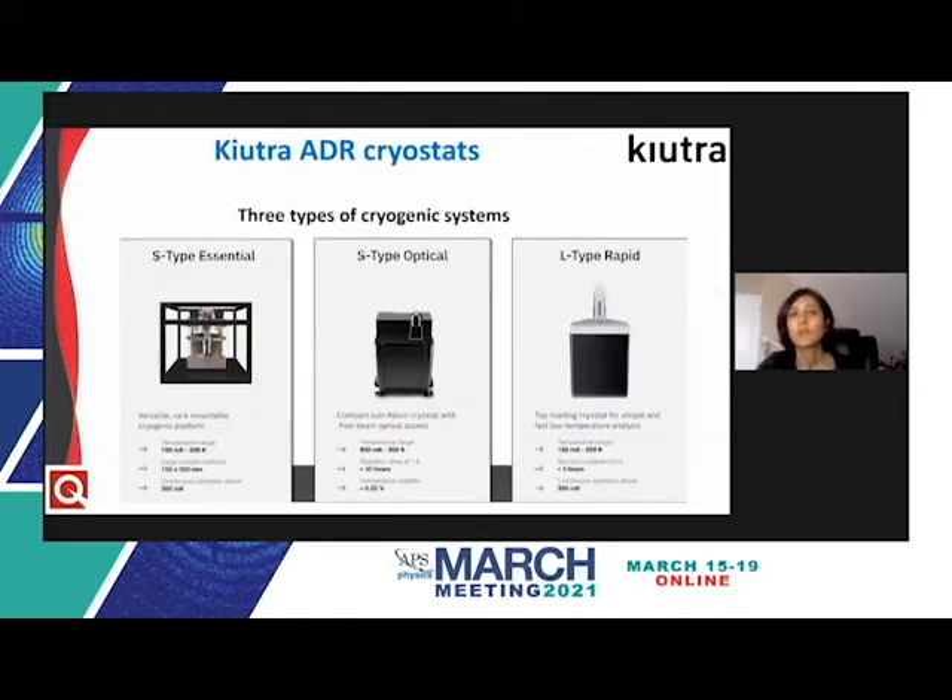Kiutra currently offers three types of cryostats: the S-type Essential, a rack-mountable cryostat with a large sample volume and continuous operation at 300 millikelvin; the S-type Optical, a compact sub-Kelvin cryostat with free beam optical access; and the L-type Rapid, a top-loading cryostat for quick low temperature measurements at values as low as 100 millikelvin.